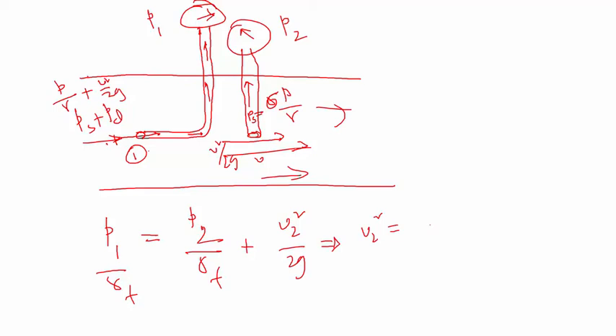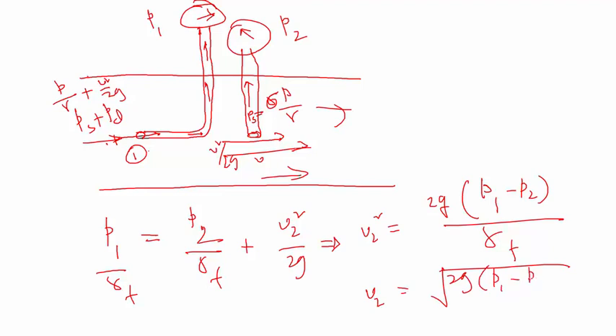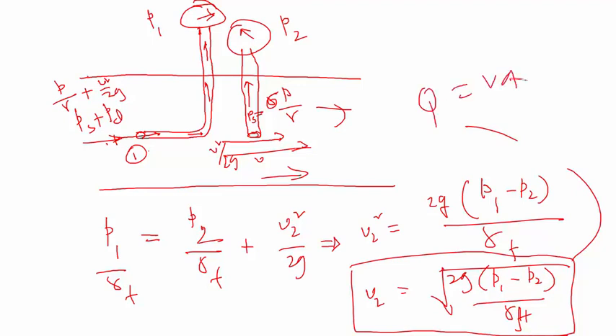So that would be 2g times P1 minus P2 divided by gamma of the fluid. So the velocity will be square root of 2g P1 minus P2 divided by gamma of the fluid. So now we know the velocity, we can calculate the flow rate.